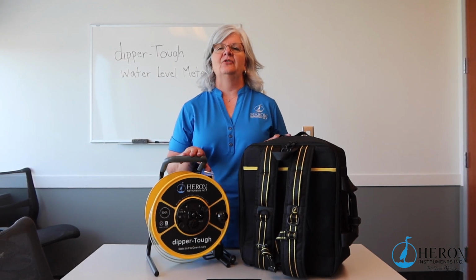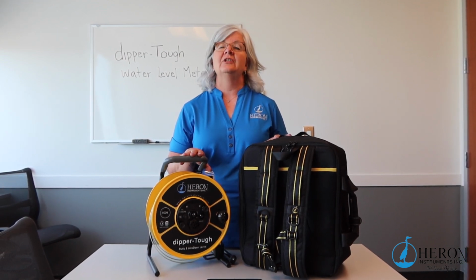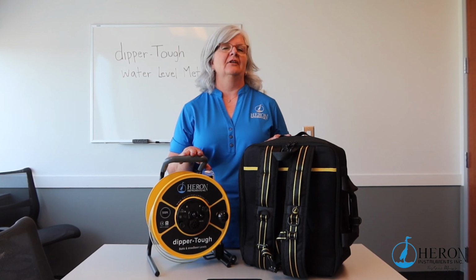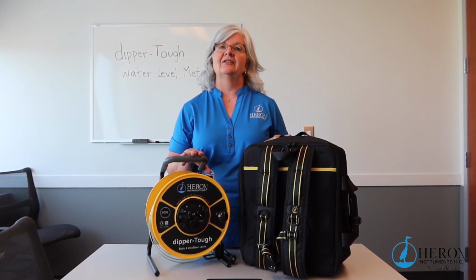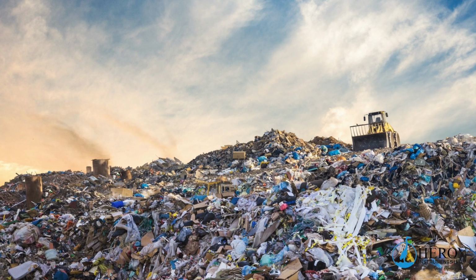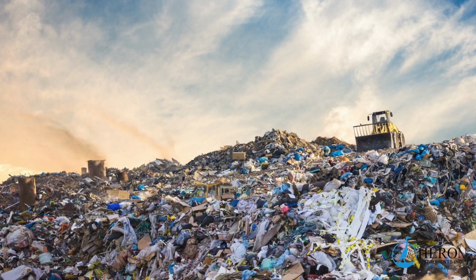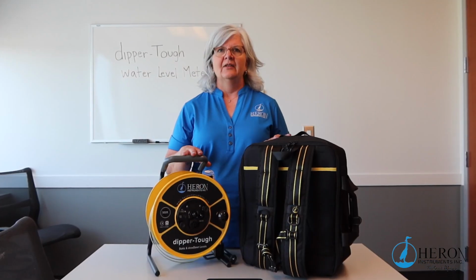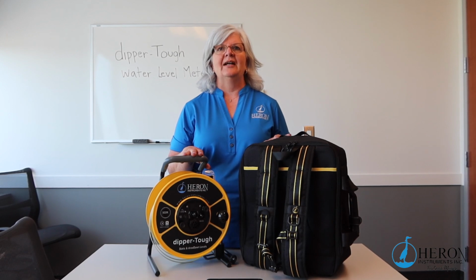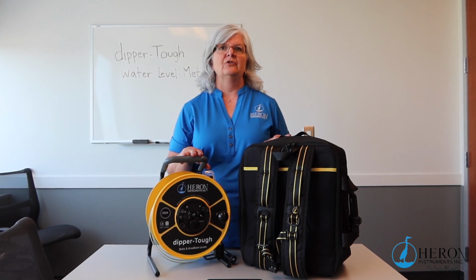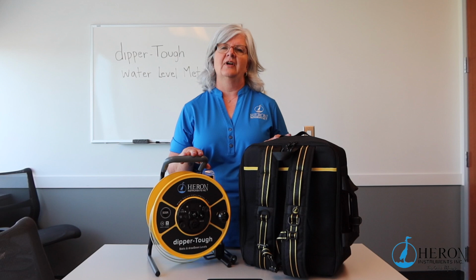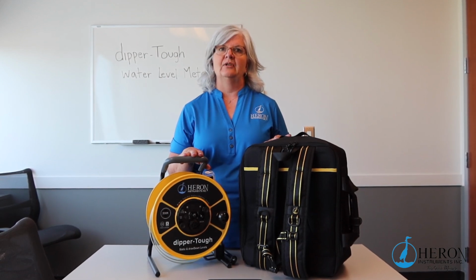Today we're going to demonstrate how to use the Heron Series 1400 Dipper Tough water level meter. The Dipper Tough was designed for our clients that need a tougher water level meter. This unit is ideal for use in remediation and landfill sites where higher temperatures and contaminants can be an issue. The premium yellow steel tape has a tougher Kynar coating to protect the markings in harsher environments, providing a longer tape life than standard tape units.